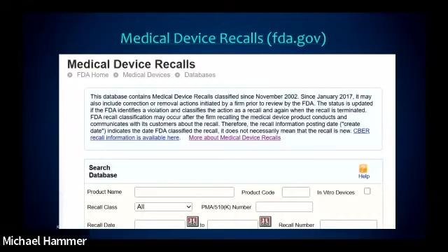So with your institutional operations, you should have a system in place so that somebody is looking at recalls that have been posted at least on a monthly basis, if not more frequently, to make sure that we're not missing anything. You can subscribe to whatever listservs you want. I get hundreds of messages from the FDA because at my office, we have to stay on top of everything that comes out on recalls. I get all sorts of stuff.